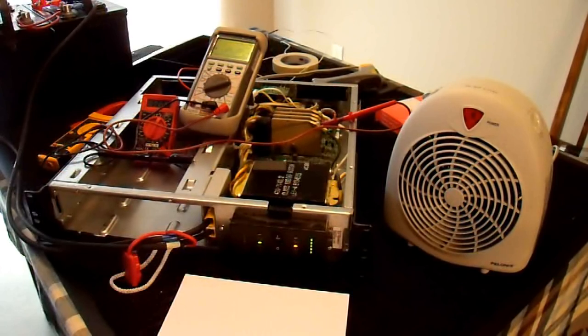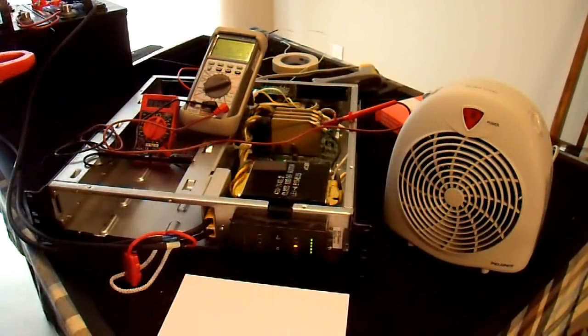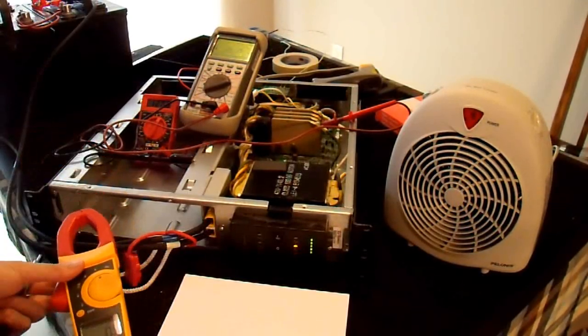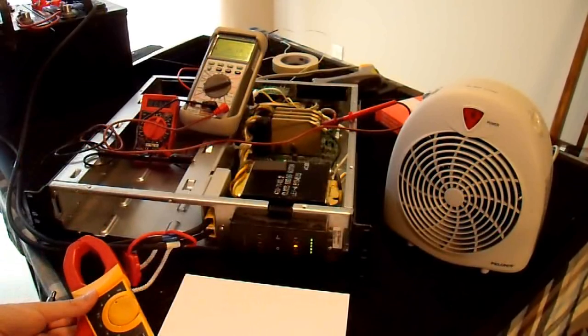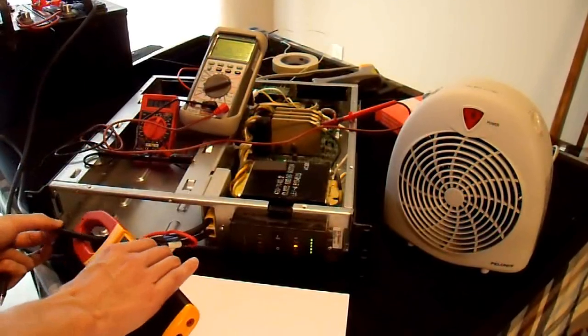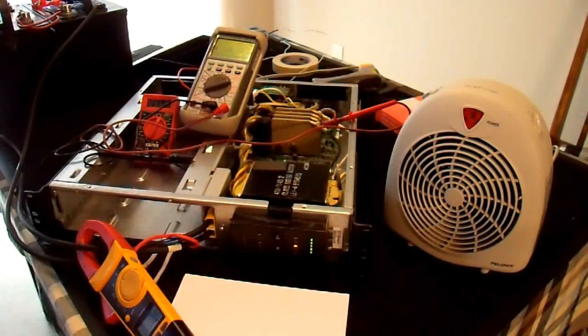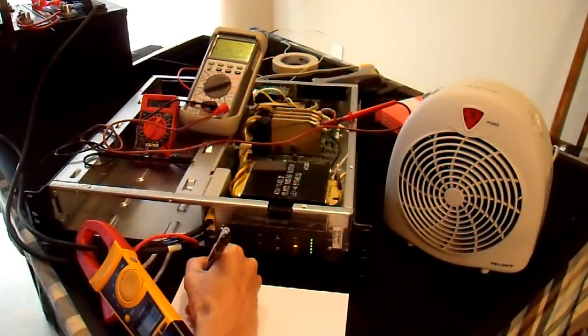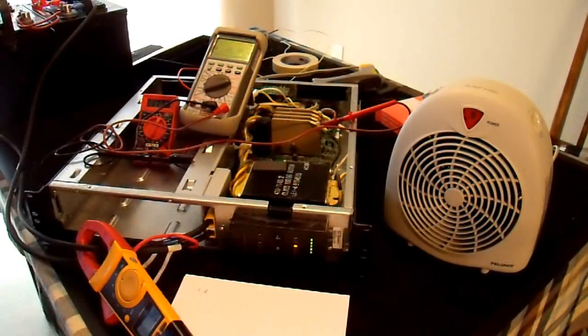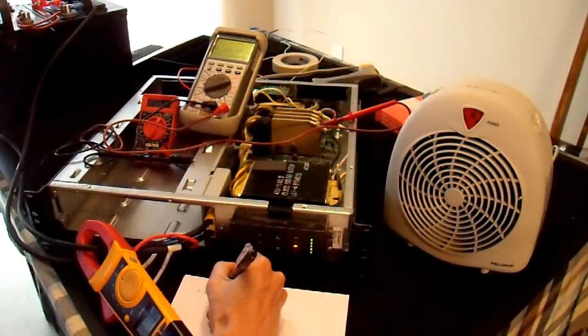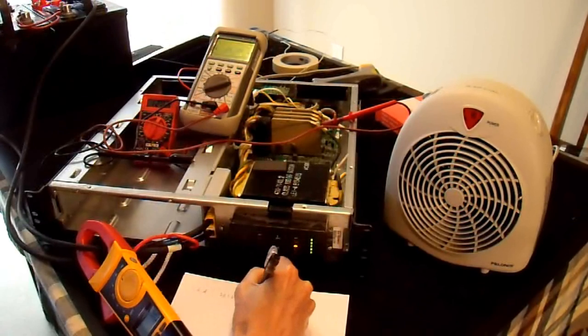Right now I have no load on it, but I want to see how much power it takes just at idle on its inverter function. So I'll take my meter, zero it out, clamp it on the cable, and I have 1.6 amps of input current at a battery voltage of 26.1 volts. That's at no load.